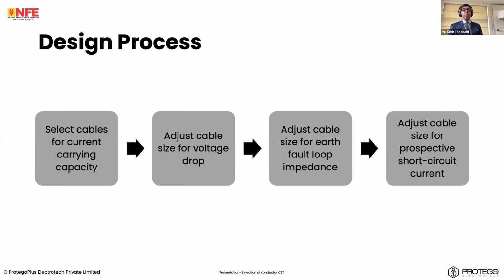Once that's taken care of, the conductors are providing the right current carrying capacity and the right voltage. But now the question is, is the earth fault loop impedance value low enough such that if there's a fault between a line conductor and a PE, or a line conductor and an exposed conductive part, disconnection by the protective device will occur in the required time? Once that is taken care of, we have to see that when there is a fault, there is a certain amount of prospective short circuit current that flows through the circuit. What happens to the cable? Can the cable withstand that amount of energy till the device causes a disconnection? So these are the four basic stages.